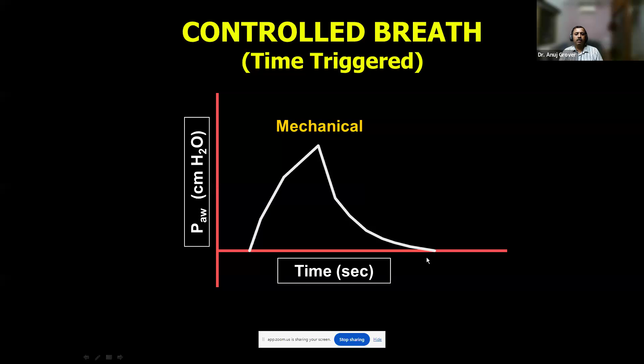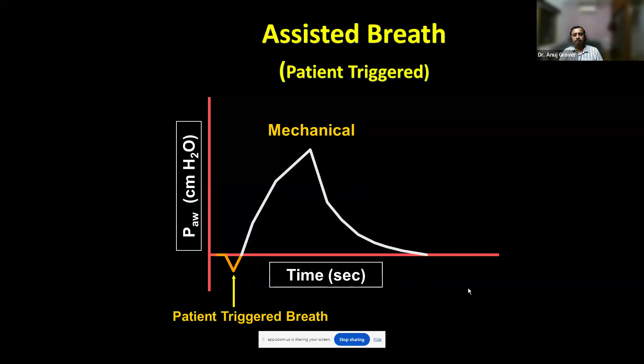What about an assisted breath? In an assisted breath, the baby starts to take a breath. There's a negative deflection, but the ventilator now supports this breath and the pressure goes up. And after the end of the inspiratory time, the pressure goes back to the baseline. So that is a patient-triggered breath.